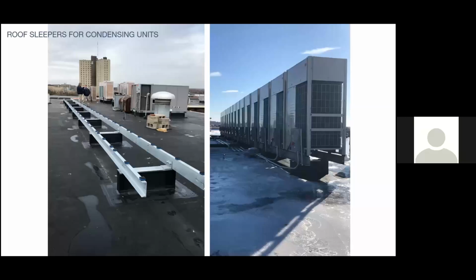So we typically try to push away from that, as firstly, most manufacturers' condenser units are all internally isolated. And then secondly, we often have a hard copper piping from our condenser units, which means any slight movement from springs could possibly cause shearing in the piping. So if any extra isolation is needed, we typically would like to go with these small neoprene pads, which we used on this job, and the condenser units just sit on those, which is pretty simple.